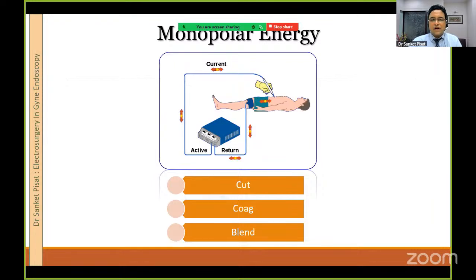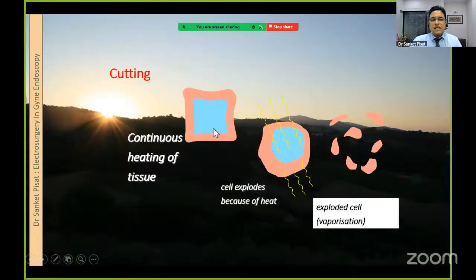You can either have cutting current, coagulating current, or blended current. So it has to be one of these three currents. And again, the principle remains the same. The current is generated from here, it will pass from here, through the active instrument to the patient, back to the return plate, and then back to the machine. So let's see cutting and coagulating waveforms and how they are actually different.